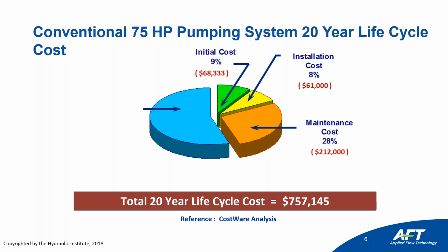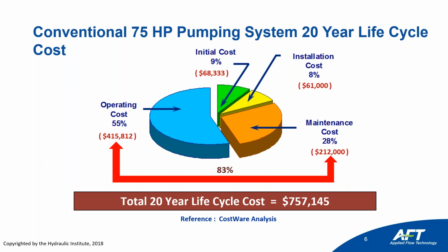Well, what does it cost to maintain it? That's a lot higher, 28%. So that includes repair costs, when your equipment fails and you have to replace it and maintain it. Last but not least, your operating costs make up the highest percentage of the total cost of the system. So 55% of the cost, $415,000, is in the operating costs themselves. And what you're going to find, especially if you were to do some creative modeling with Fathom, is it's very quick and easy to see how you can dramatically improve the cost savings of these systems. So your operating costs and maintenance costs make up 83% of your total costs.